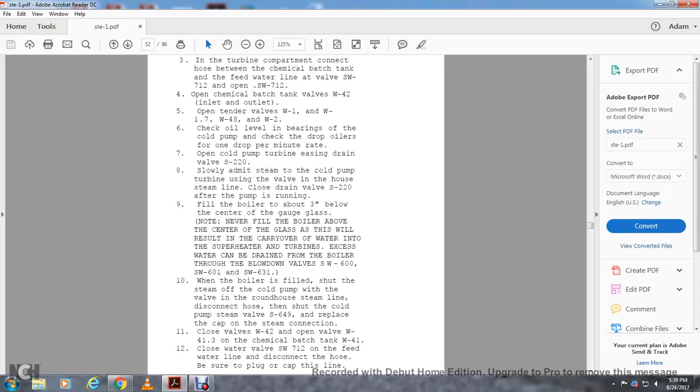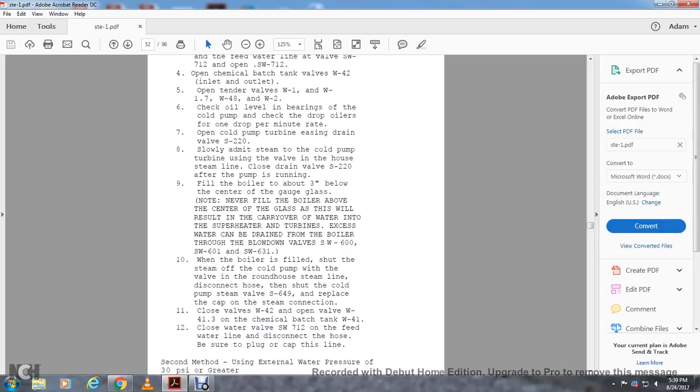Shut the cold pump steam valve S-649 and replace the cap on the steam connection. Close valve W-42. Open valve W-41.3, the chemical batch tank valve W-41. Close valve SW-712 on the feed water line and disconnect the hose. Be sure to plug or cap this line.